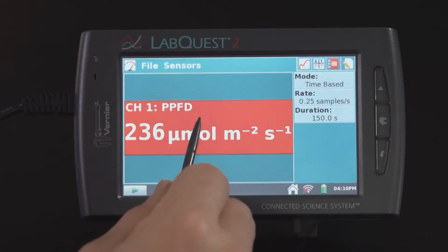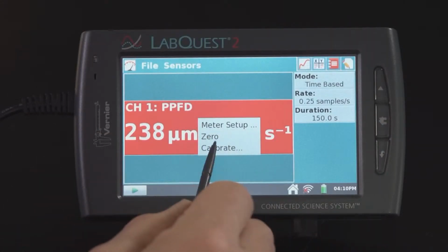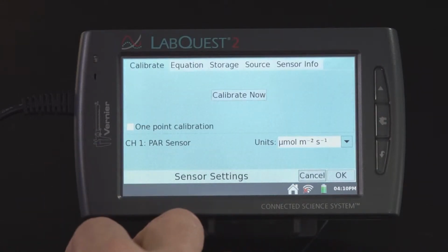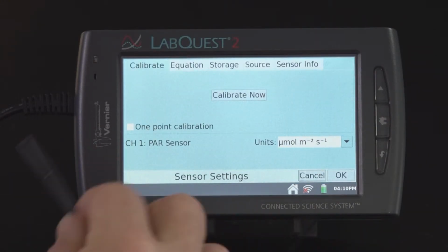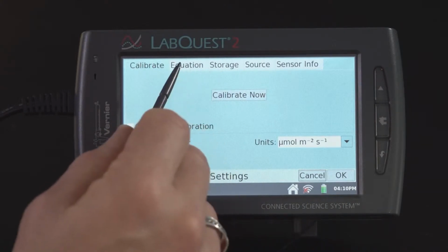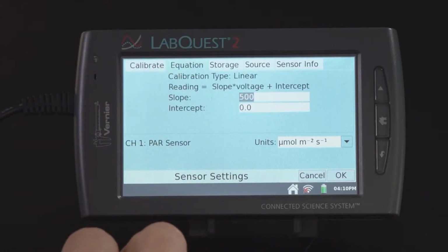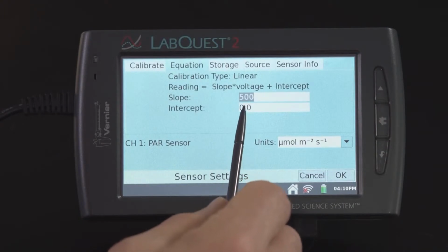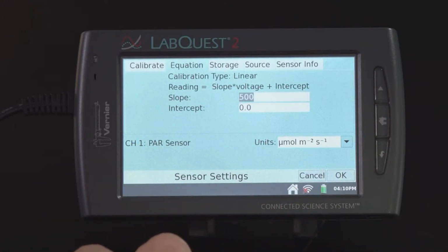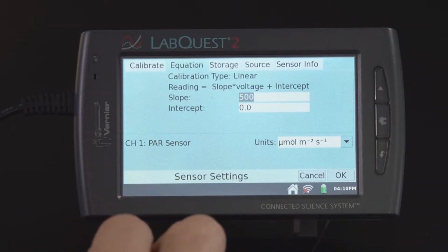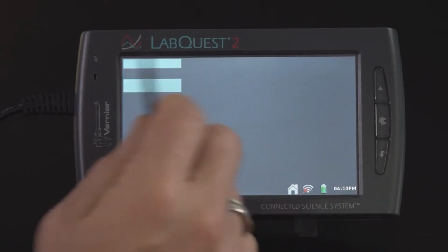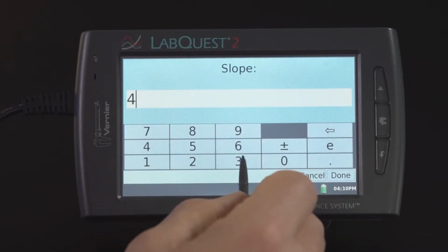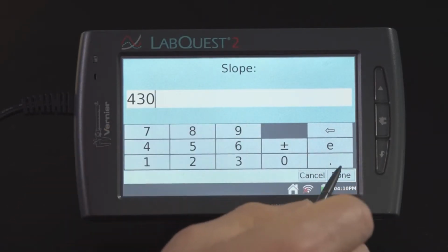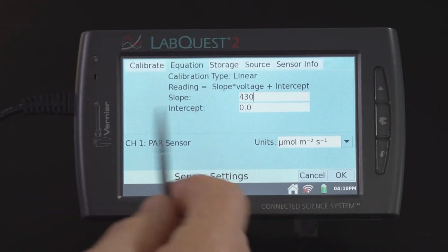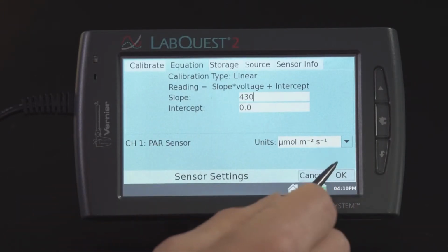I would just tap here on the meter screen, select Calibrate, and then go to the Equation tab, which is located right here. And you can see right here I have the slope and the intercept. Now, all I want to do is reduce the slope by about 14% or change it to 430. Next, I'm just going to select OK to change that slope.